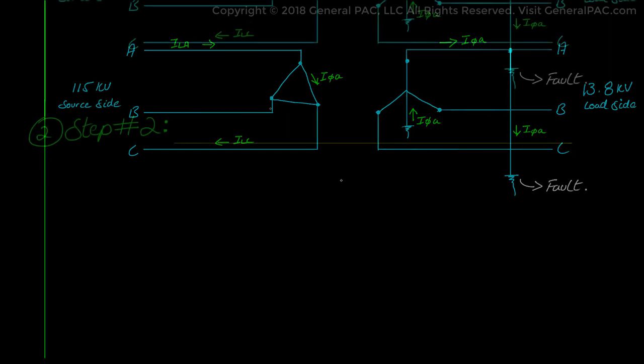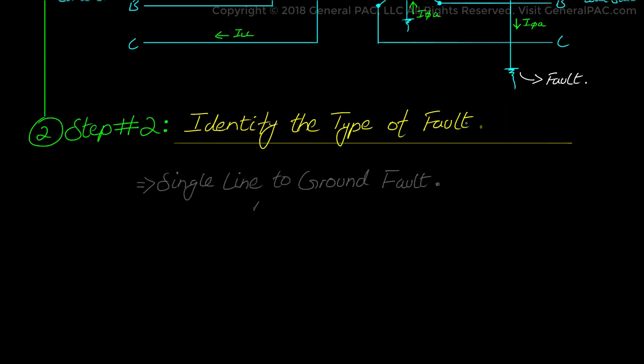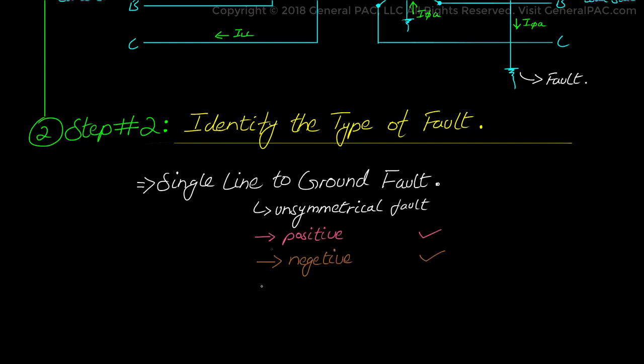Next we move to step number 2, which asks us to identify the type of fault involved. We have a single line to ground fault, which is an unsymmetrical fault — meaning an unbalanced fault type. This type of fault produces all sequence quantities: positive, negative, and zero sequence components for both current and voltage quantities.